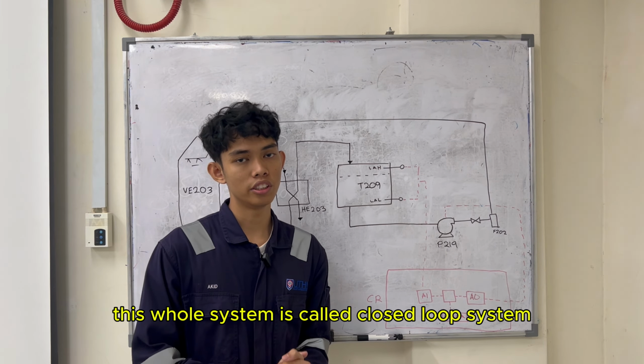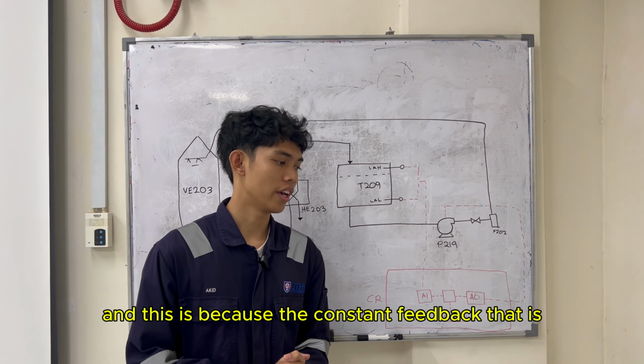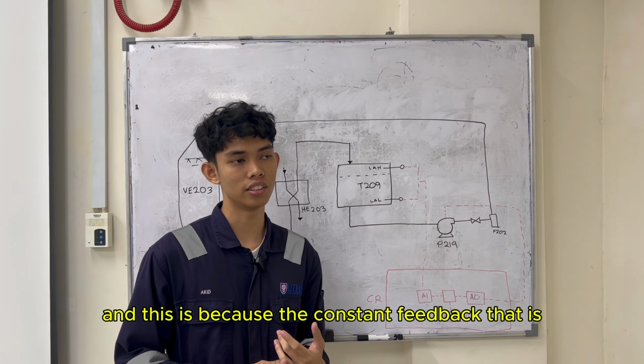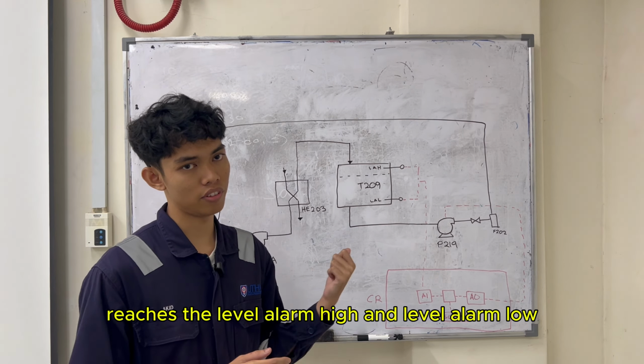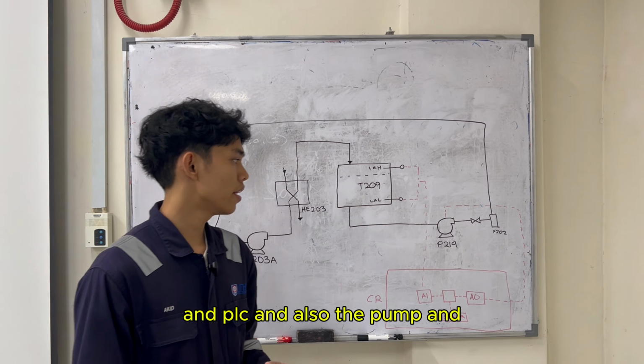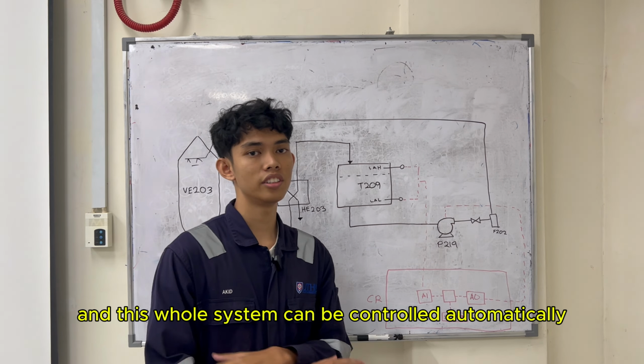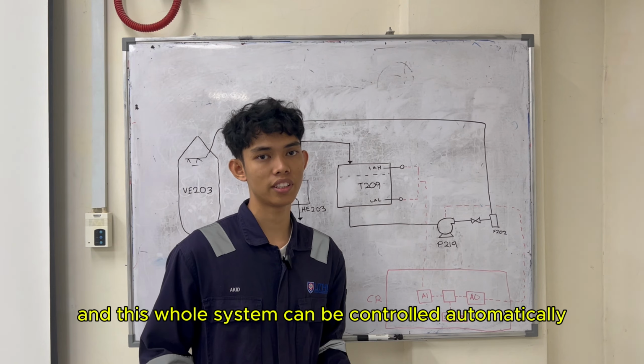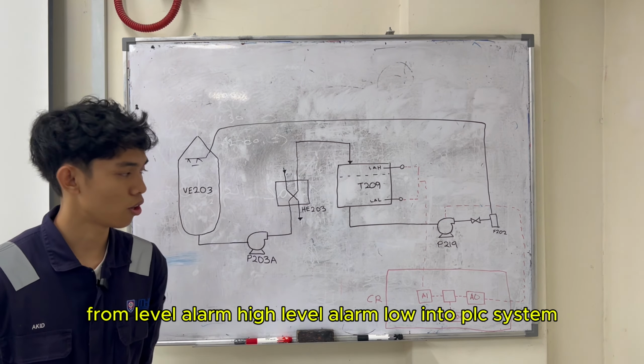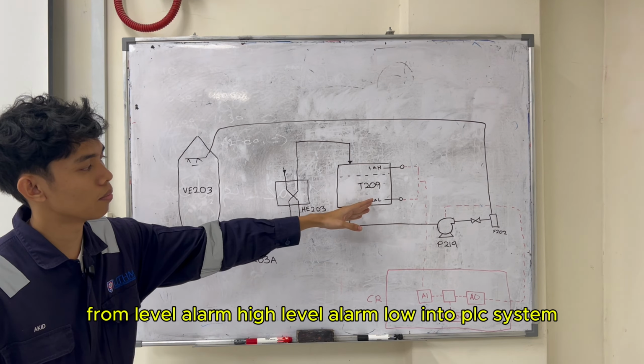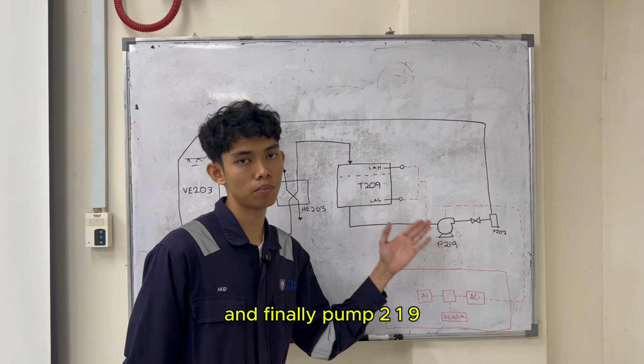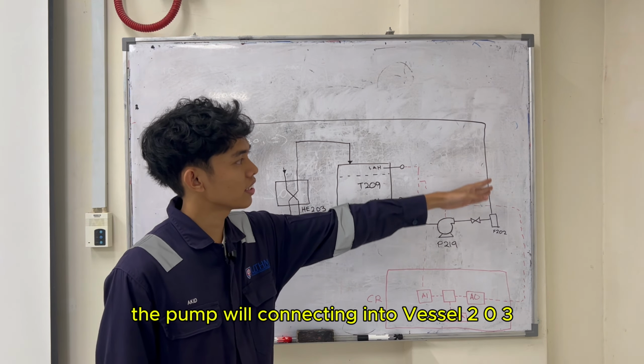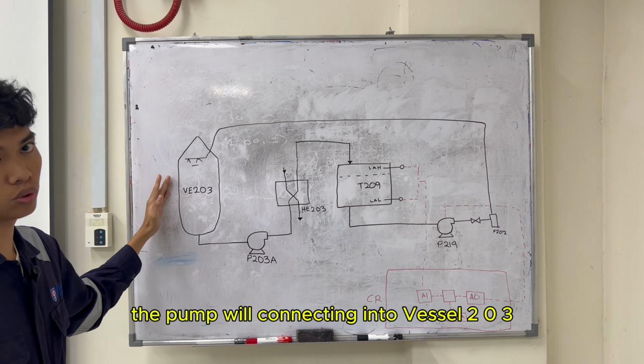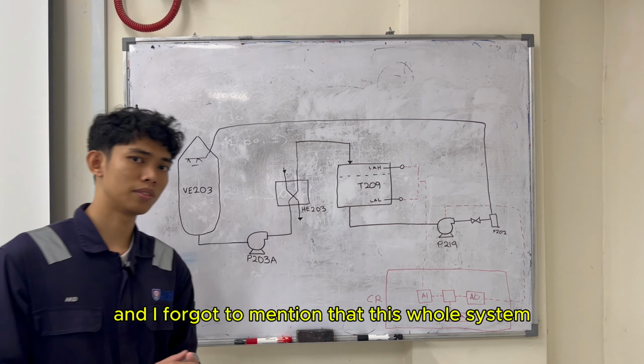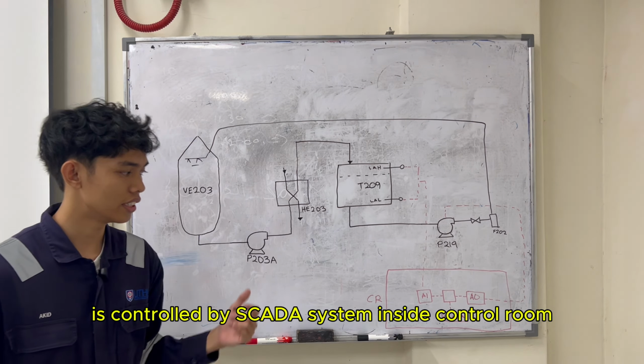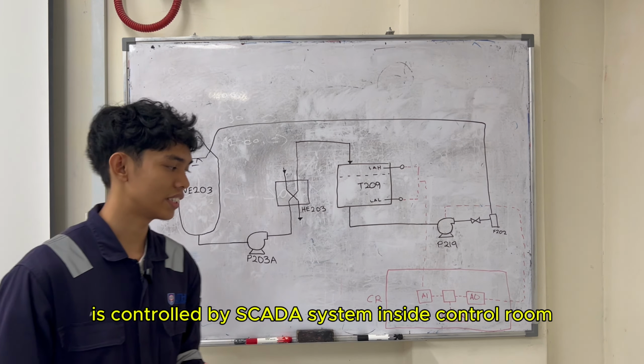This whole system is called a closed loop system, and this is because of the constant feedback that reaches the level alarm high and level alarm low, the PLC, and also the pump. This whole system can be controlled automatically and manually, from level alarm high, level alarm low into the PLC system, and finally pump 219. The pump will connect into vessel 203. And I forgot to mention that this whole system is controlled by the SCADA system inside the control room.